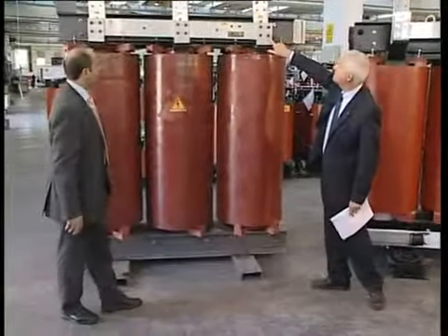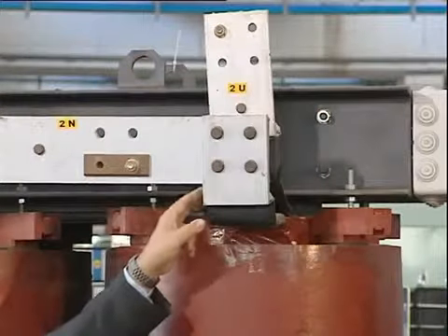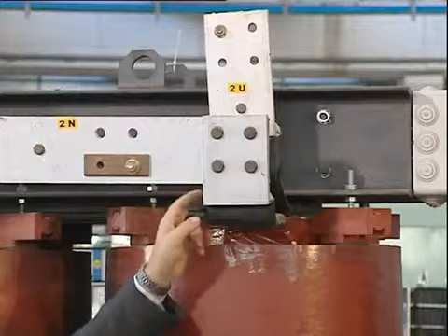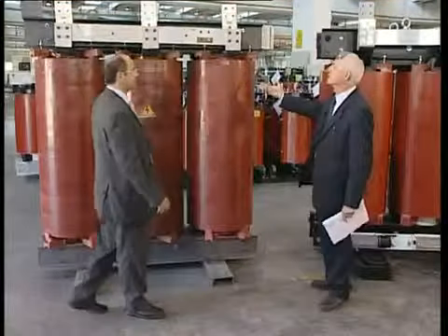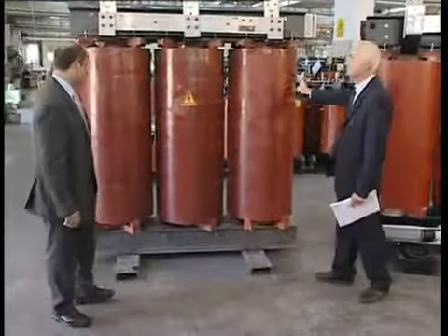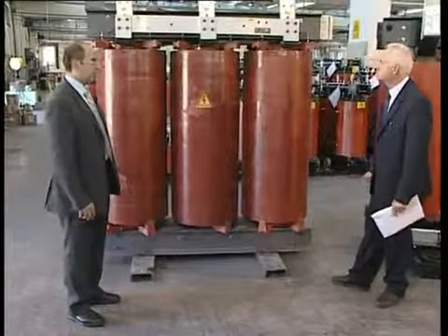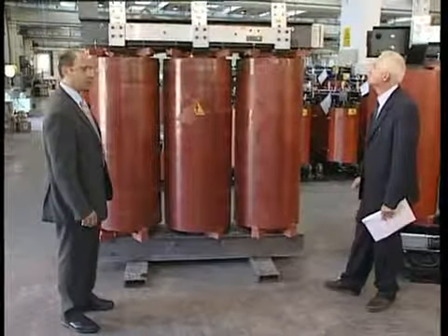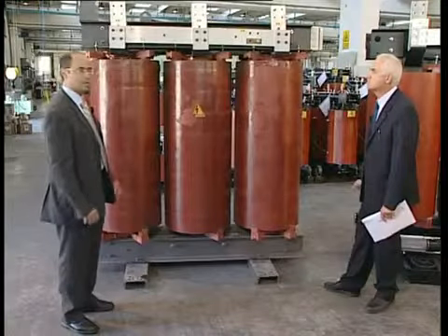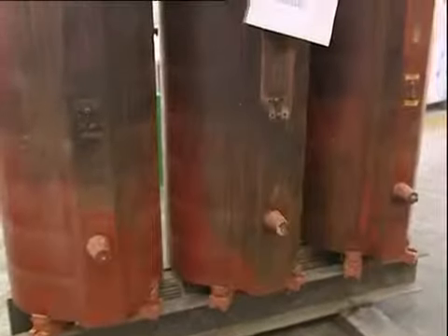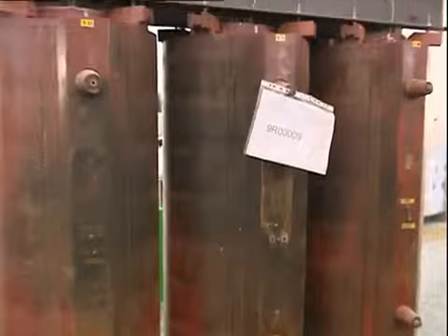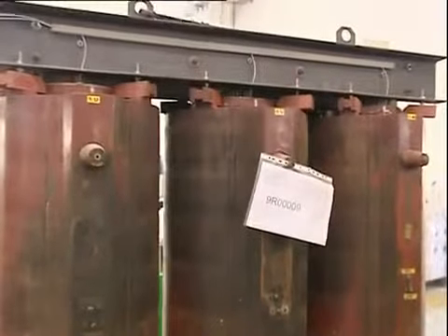What about these nuts? If we take a close look at these nuts, we can see how they have been well cooked by the transformer's overheating. Has this transformer operated for many years? This transformer was produced approximately 2 years ago, but it worked only for a few months, unfortunately. Why? Because the central low-voltage winding fused as a consequence of overheating.